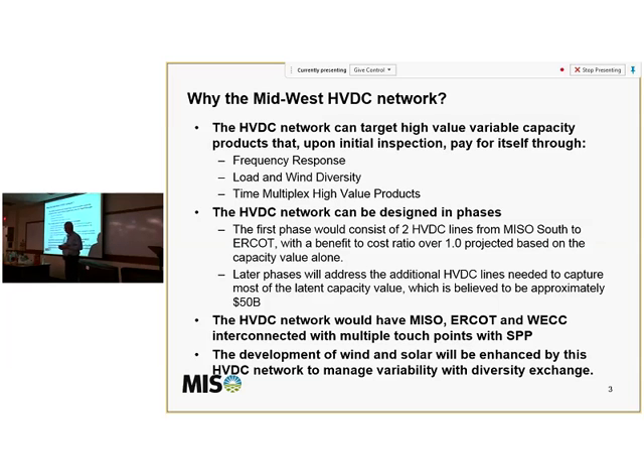But if you go to three lines, it is almost always less expensive to build a higher voltage, if you can load those three lines economically. And the caveat is you have to be able to load them. So if you have three lines and you lose one, the loading on that line pre-contingency would be 2/3 of the rating of the lines. And if you have an AC system in there, it's n-1 times the rating of the line plus the AC capability. So you have to build a system that won't overload anything that's there already, or if there's nothing there already, it holds its own contingency. But generally speaking, if you don't have three lines, economically it won't work.